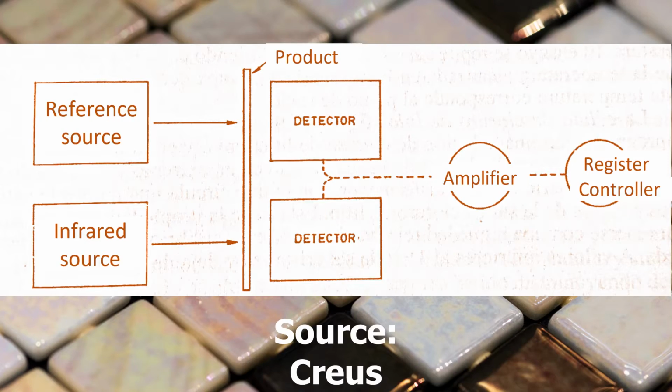In the infrared method applied in papermaking, an infrared source emits a beam of rays towards the surface of the material whose humidity is to be measured. The wave emitted is selected in such a way that the water contained in the product absorbs the maximum infrared radiation, while the cellulose absorbs the minimum. Thus, a detector captures the radiation that passes through the material and indicates the corresponding humidity.